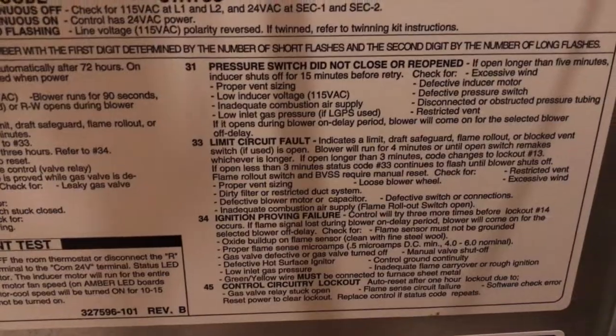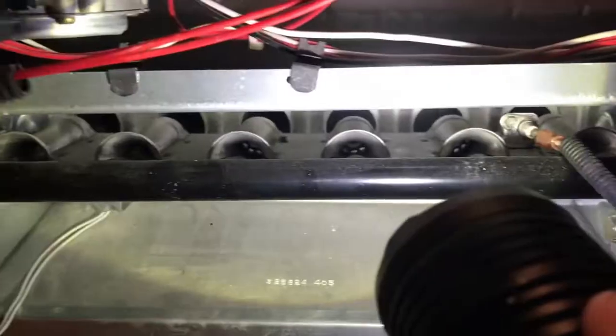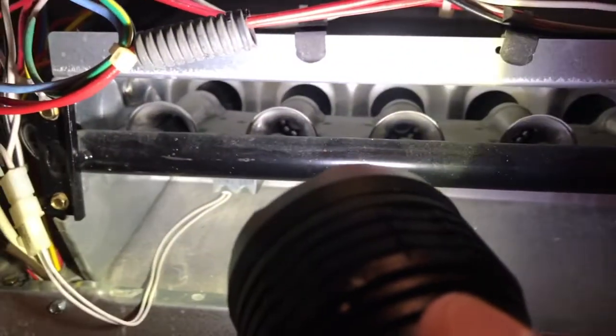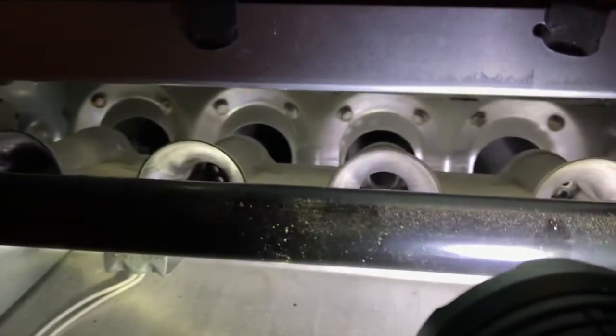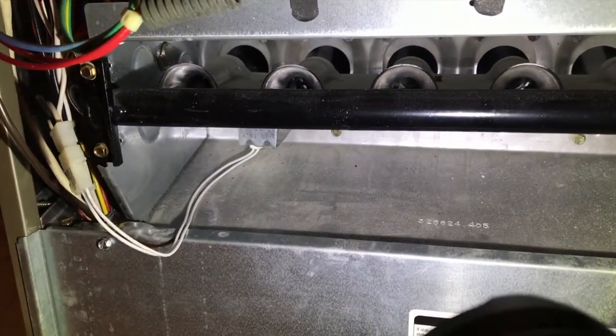You could have inadequate combustion air supply or a flame rollout switch open. Inside here are all of your burners — when everything's working properly, this is all lit up. That sensor right inside there is designed for any rollback or loose flames that get out of sequence and fly out of control in this area. You have an additional one up top right inside there as well. If your flames are getting out of whack and coming out in this area, those relays will trip or fault out — and that could easily be caused by an extremely windy day.